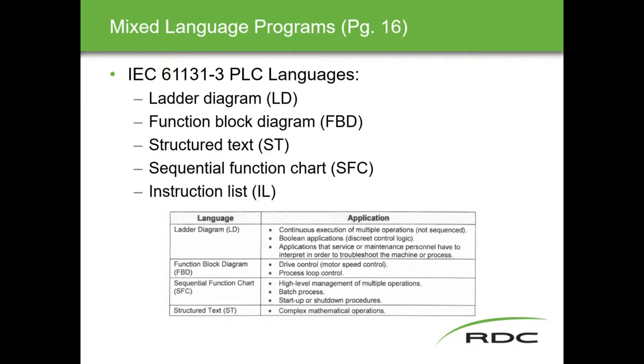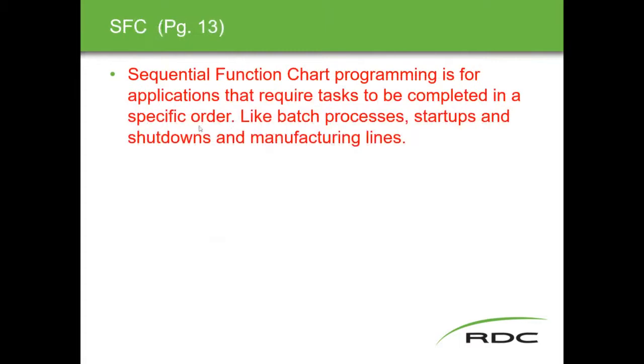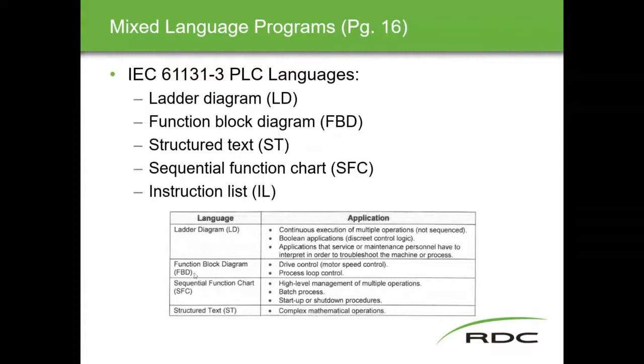Okay, this graphic I added in here because we left off saying SFC is good for this kind of stuff. This little chart tells you all in one what the best applications are for the different types of languages. Ladder diagrams: continuous multiple operations, not sequenced, you'll notice. Function blocks: drive control or process loop control. That's because we have that PID block that we can drop in there that works so well. SFC: batch processes, startups, shutdowns, etc. Structured text: complex math operations.